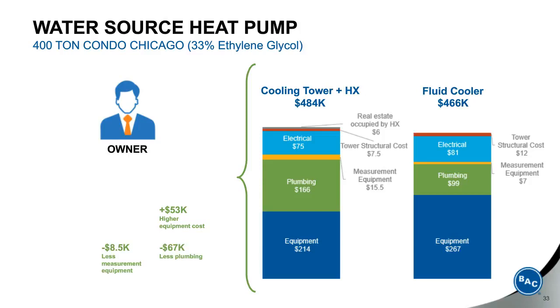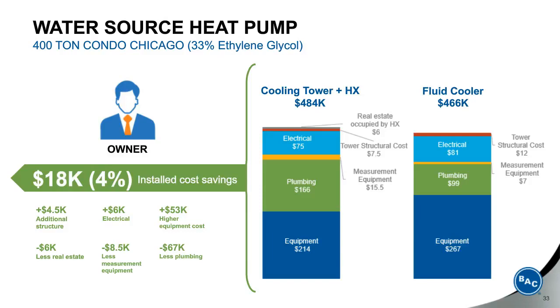But this is more than offset by the $67,000 less in plumbing and piping, $8,500 less in measurement equipment required. Electrical did go up $6,000 for the fluid cooler option, but you offset that with the lower real estate costs by reclaiming part of your building for rentable space, and $4,500 for the additional structure required to support the fluid cooler. The total installed cost savings came out to $18,000 or 4% of the total installed cost.